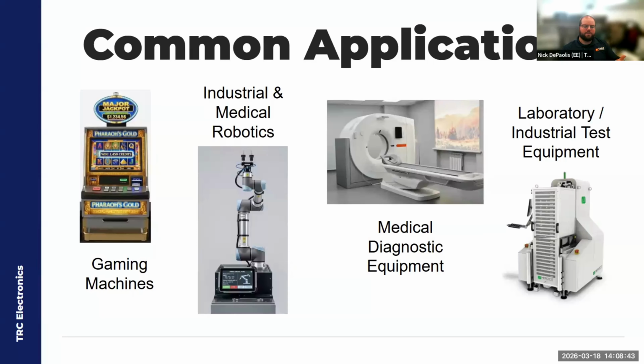A lot of these machines, if you try to do that with separate power supplies, you're going to run into leakage current issues where you won't meet the industry requirement to stay within a certain threshold. So modulars are very effective, because you can put one in there and it's going to have leakage below that threshold more often than not, preventing you from running into that agency requirement later on. Otherwise you'd have to do a whole redesign for your system, to meet an agency or safety requirement. Exactly.